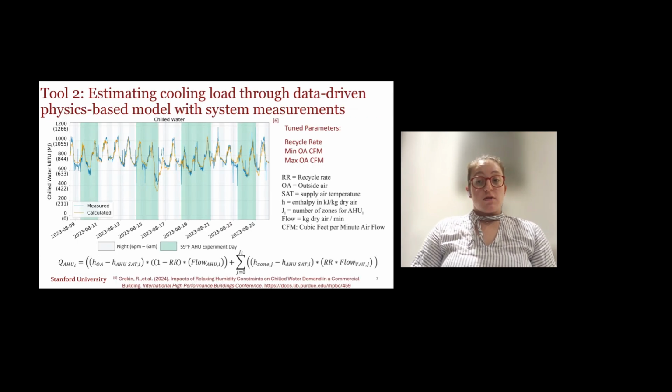The second tool I'm using is based on a data-driven, physics-based model, which I developed during these experiments to understand the energy impacts of implementing these adjusted set points. Here, I'm showing you the comparison of the model results and the actual chilled water load from the experiments run in Texas. As you can see, there is pretty good agreement. Unfortunately, we don't have time to dive into all the details of the model right now, but if you'd like to learn more about this, please find me afterwards.